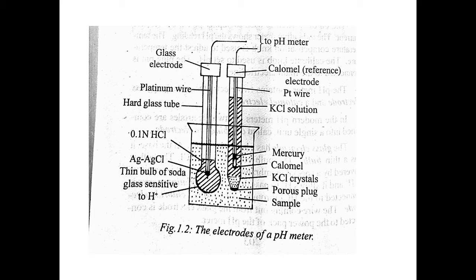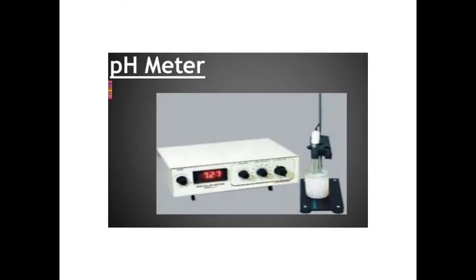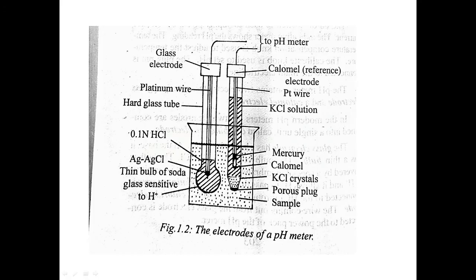Okay, so your pH meter consists of what? A power pack, right? And as I said, a pH meter can be digital or manual. A pH meter consists of a power pack and two electrodes. What does the power pack consist of? An on-off switch, like here we can see. This is a power pack or display unit having an on-off switch. Then there is a temperature control knob, which we call the temperature compensation knob. Then there is a calibration knob and a plug pin, with which it is connected to an electric supply. Okay. Now a pH meter originally used to consist of two electrodes, as I said, glass and calomel.